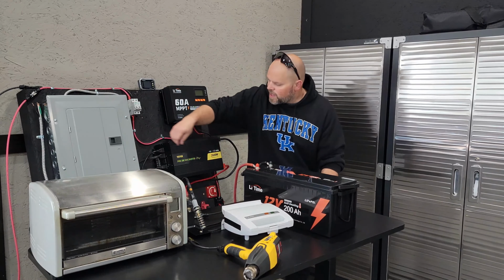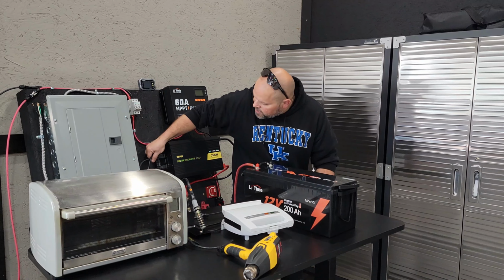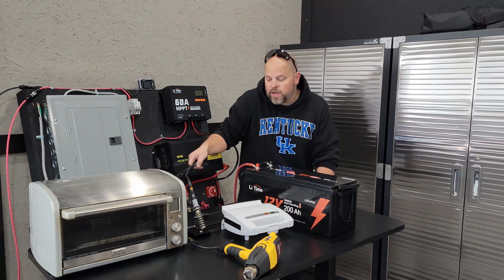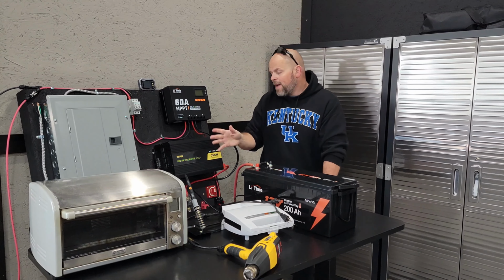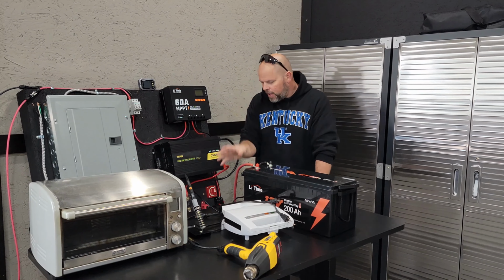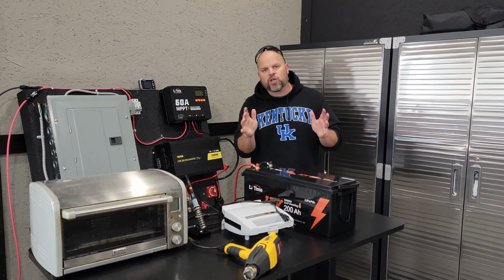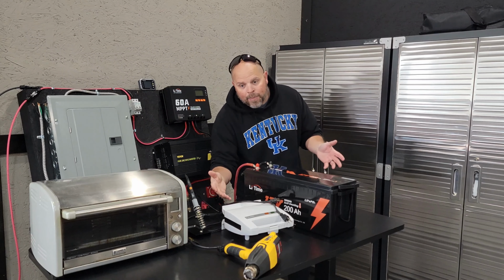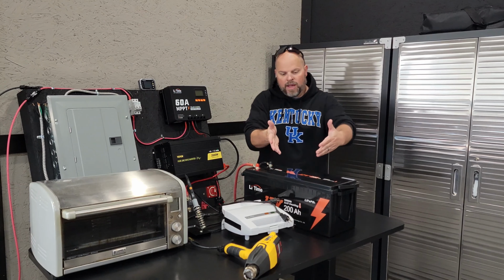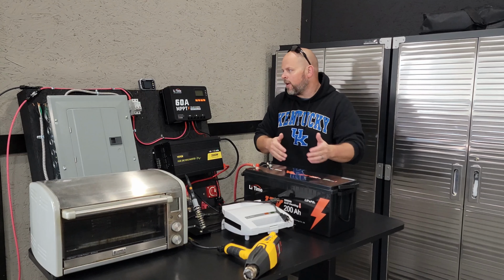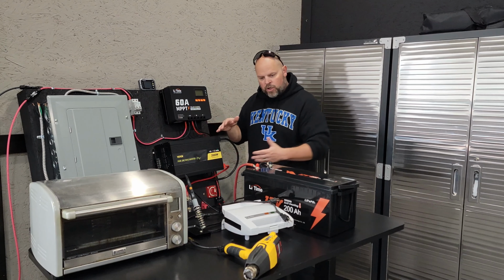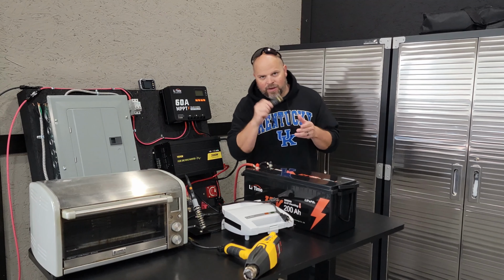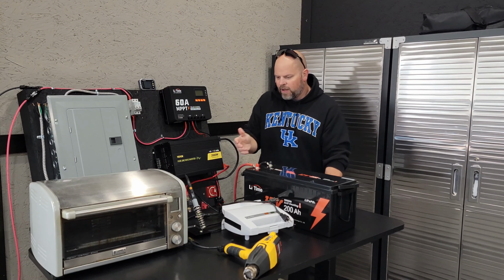And that's why we put protections in place, is to protect ourselves when we're doing stupid stuff. So that was stupid, I should have thought better on the fuse itself, but it's a good example of what could happen if you didn't have that in there and the BMS failed in your battery, or something failed in your inverter, then you've got a fire going on. That's why you put these protections in place.